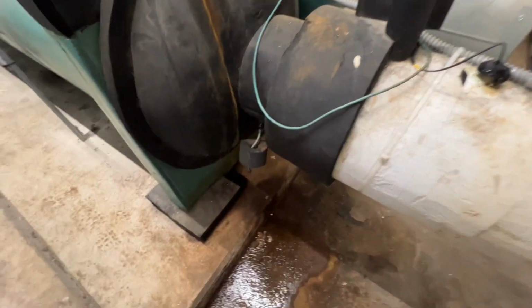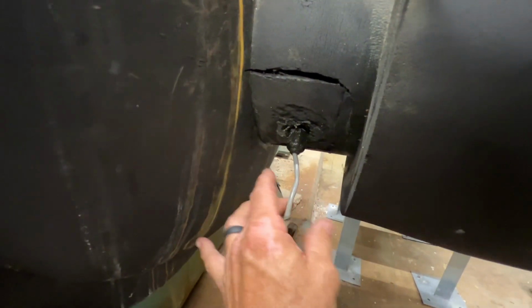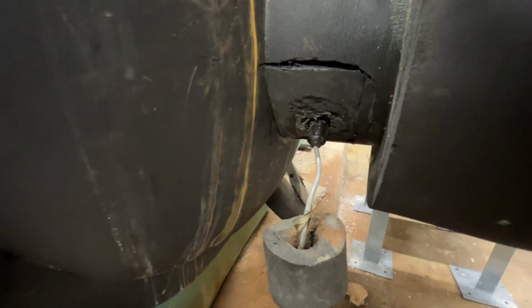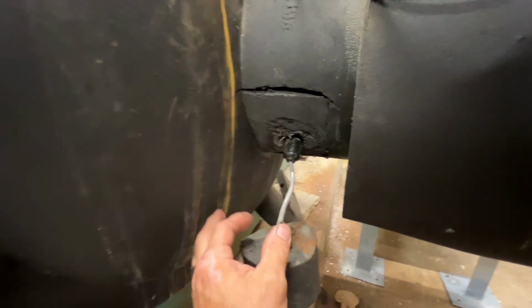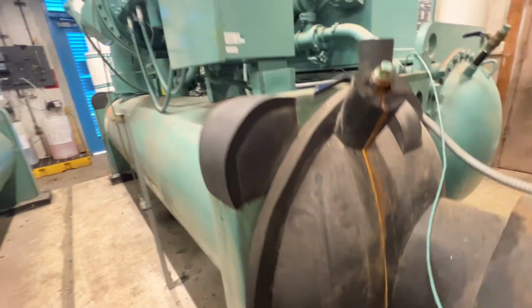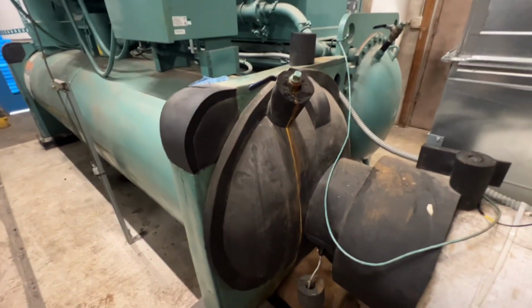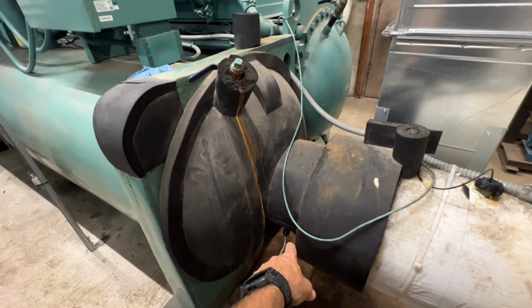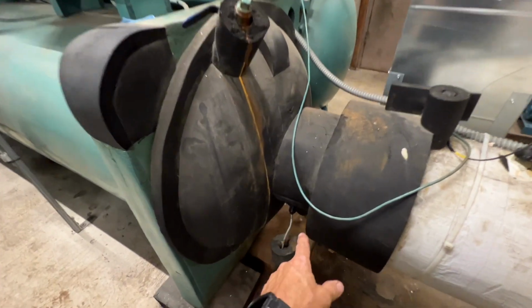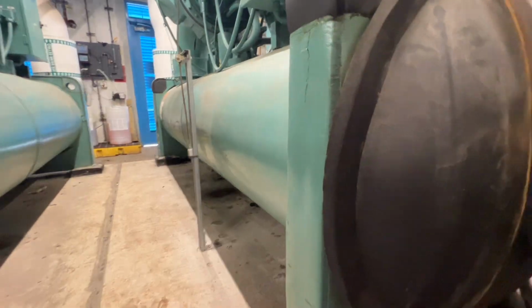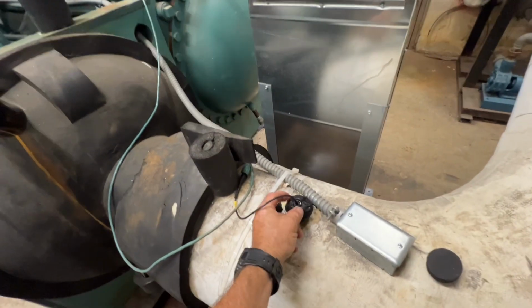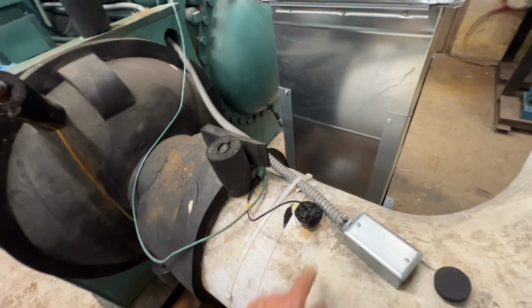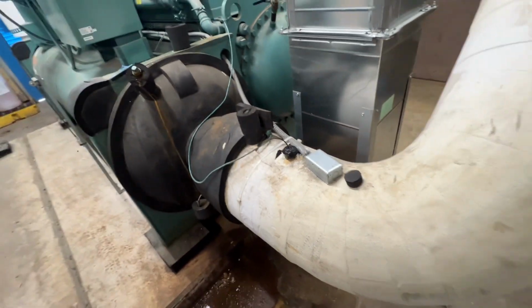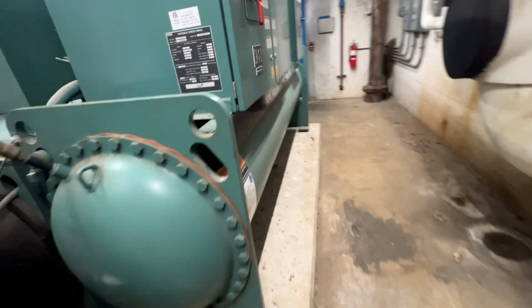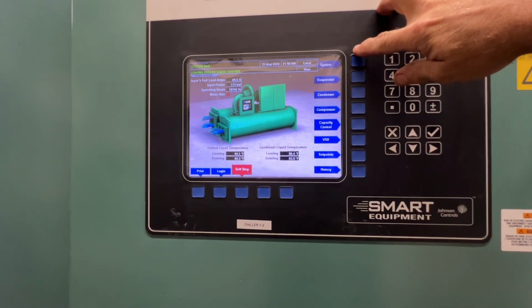And on this chiller 2, we found out that these temperature sensor wells are leaking. He was going to replace that because this sensor was reading too warm, causing chiller 2 to basically overcool. So that's leaking, so we couldn't replace that without shutting down the whole system. And he believes that the well may be cracked, this one and on the entry. So we utilized the thermometer well and just put our new sensor in there. And that seemed to be working okay for now. They're going to come back and do some more work, but this is our chiller 2.